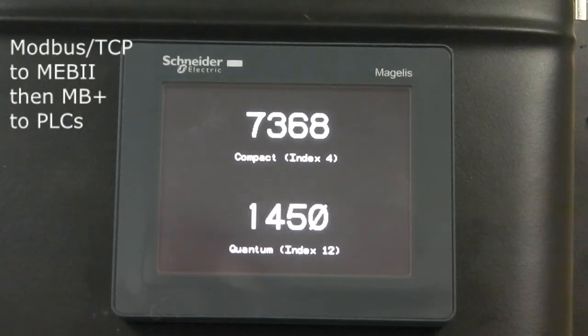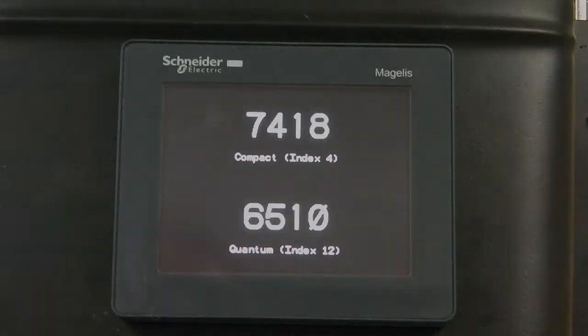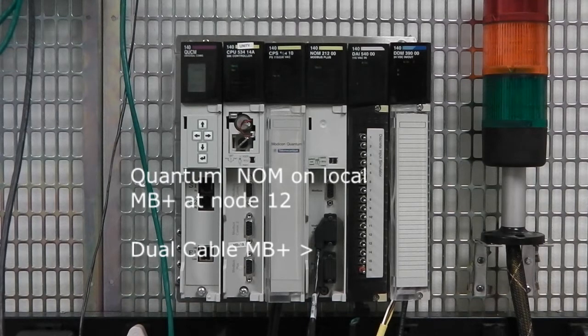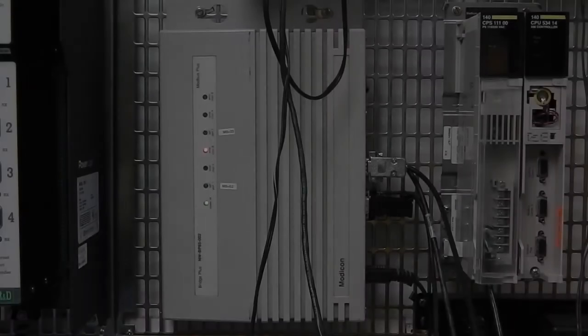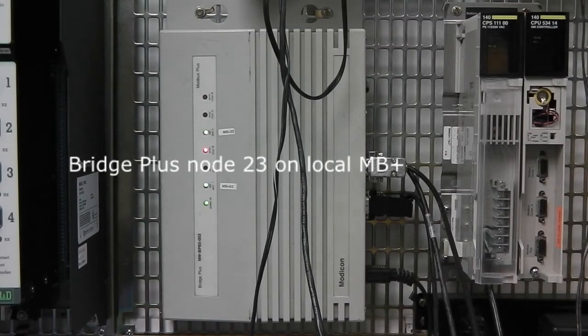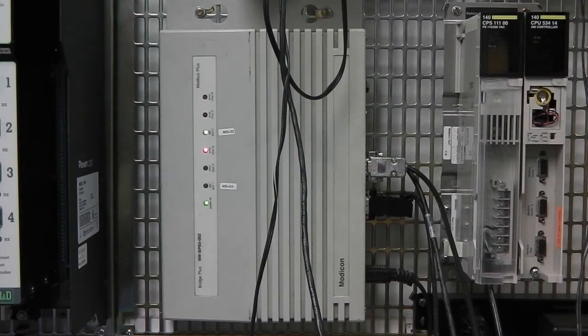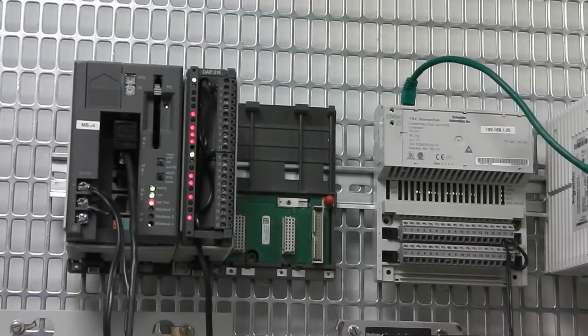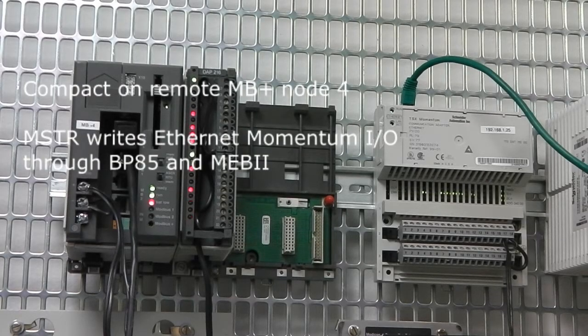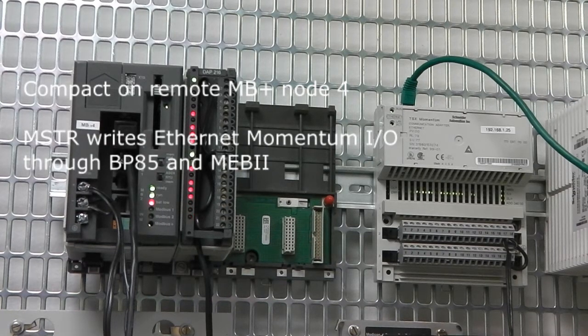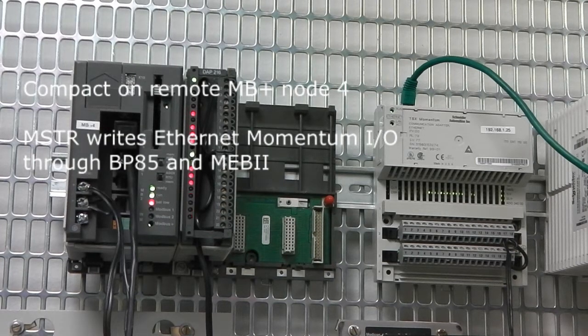The screen shows a timer value from each PLC. The Quantum PLC is connected through a NOM at node 12 using dual cabling. A Bridge Plus is located at node 23. The Compact PLC is on the far side of the Bridge Plus at node 4. The Compact is also controlling the Momentum Ethernet I/O using an MSTR to write the data through the Bridge Plus and MEB2 to Ethernet.